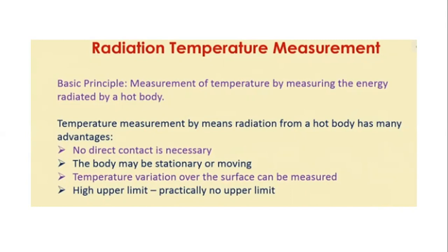The metals used in a thermometer have a limited withstanding temperature. If we place it in a medium above that temperature, the thermometer wire will melt and be destroyed. So that is the disadvantage of using thermocouple and RTD at higher temperature ranges.